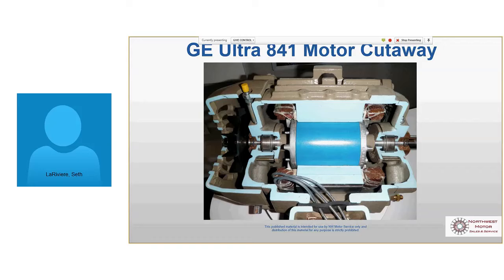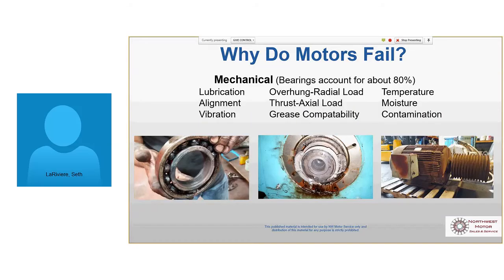So let's talk a little bit about motor failure. Most motors fail due to mechanical reasons, not electrical. And it's usually the bearings or something associated with the bearings. They either got dirty, contaminated, they weren't re-greased, or they were over-greased. Over-greasing really causes more motors to fail than under-greasing, if you look at the stats on mortality on motors.